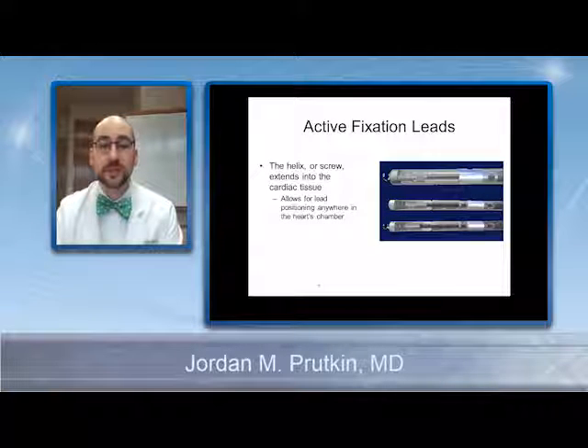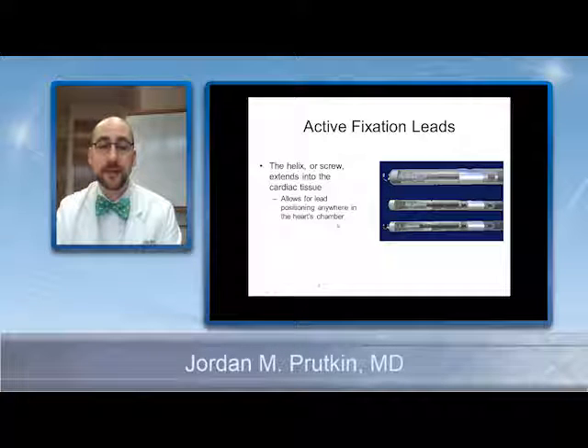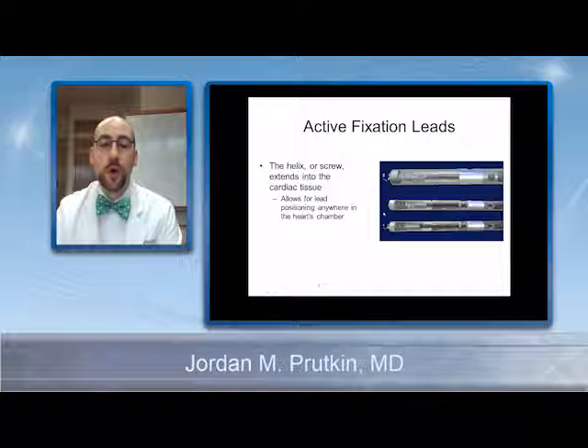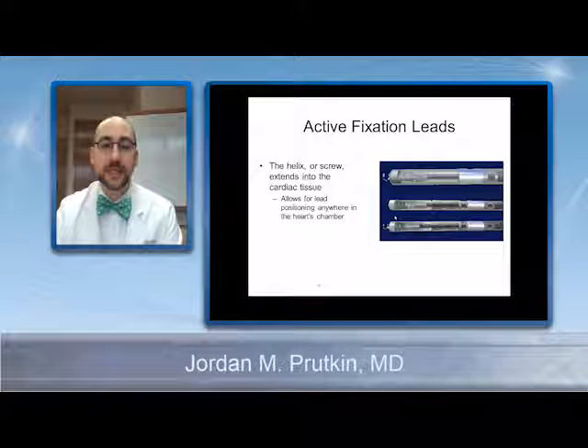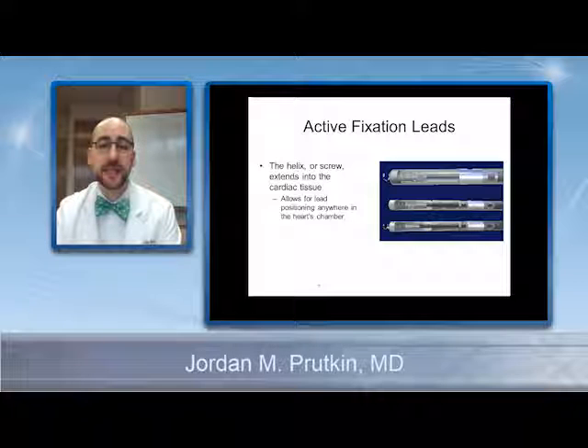There's a couple different types of leads. There's active fixation leads or passive fixation leads. Active fixation leads have a screw on the end of them, and either you can rotate the whole screw, or there can be just a part of the lead that, when you implant the device, you're able to turn so that it can extend and retract the screw. Here it's extended, and then you can retract it back if you need to reposition it. The benefit of an active fixation lead is that you're able to place that lead anywhere in the heart chamber because there's a screw that you can attach the lead into.